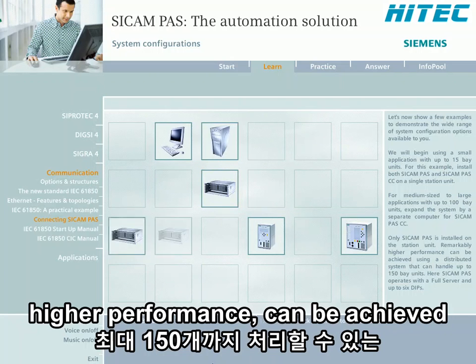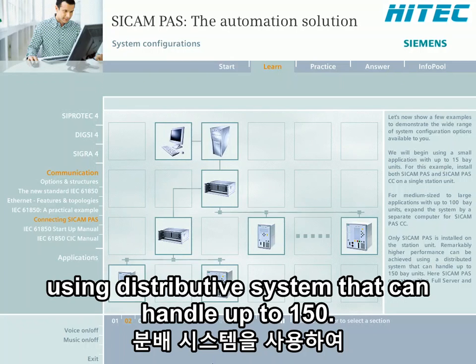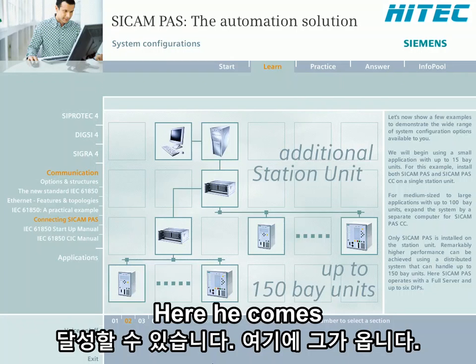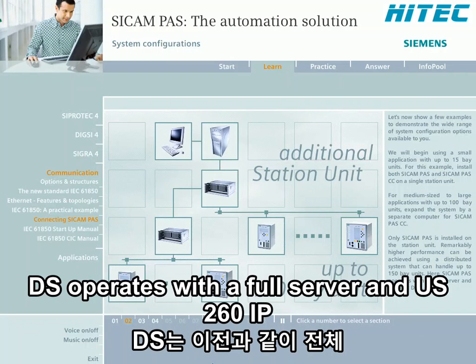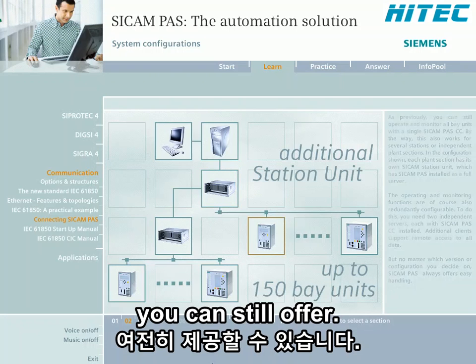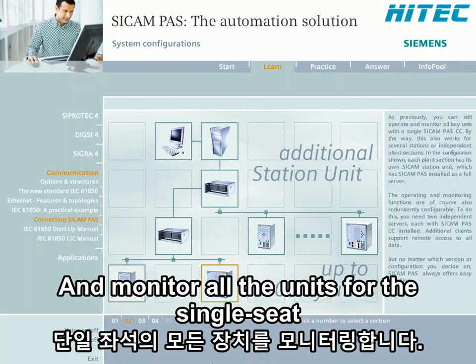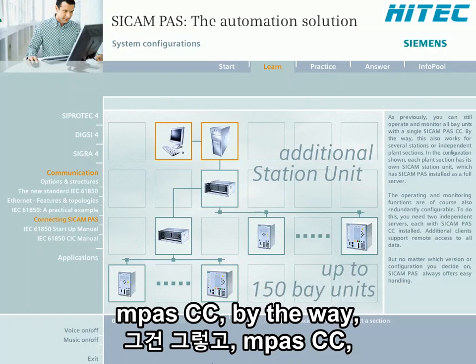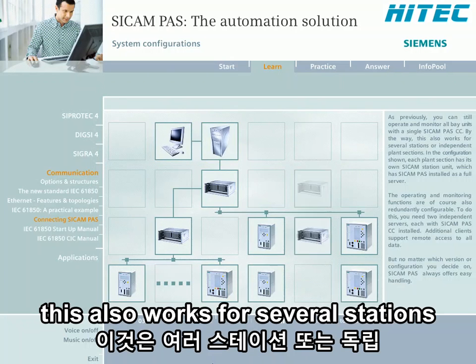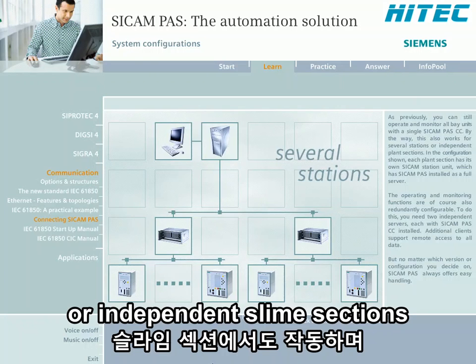Remarkably higher performance can be achieved using a distributed system that can handle up to 150 bay units. Here, SICAM PAS operates with a full server and up to 6 DIPs. As previously, you can still operate and monitor all bay units with a single SICAM PAS CC. By the way, this also works for several stations or independent plant sections.